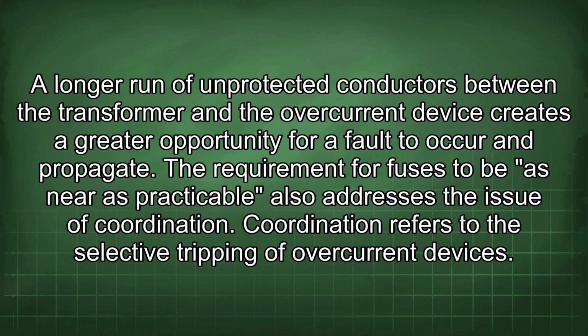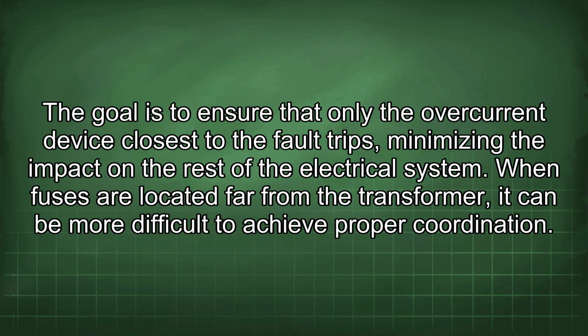A longer run of unprotected conductors between the transformer and the overcurrent device creates a greater opportunity for a fault to occur and propagate. The requirement for fuses to be as near as practicable also addresses the issue of coordination. Coordination refers to the selective tripping of overcurrent devices. The goal is to ensure that only the overcurrent device closest to the fault trips, minimizing the impact on the rest of the electrical system.